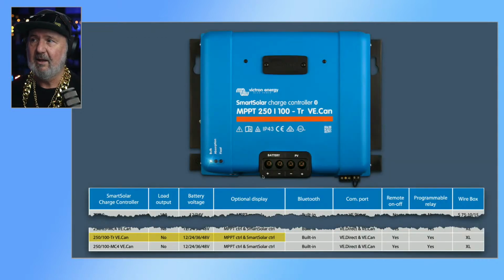So is that happening? Very popular products such as Victron's Smart Solar and many other brands do not have this functionality yet. Correct me if I'm wrong, guys, because I'm not a Victron installer these days, but only the RS450s had an earth fault detection function, from my memory, which are their big units. They have a 100 and 200 amp output, and they also had a 450 volt input, so they can definitely go well into the LV range. So you're connecting a 48 volt, in this case, it can go down to 12 volts. You see the range at the bottom there. A 12, 24, 36 or 48 volt battery to an LV array, you've now got a potential, under fault conditions, of having LV turn up on that battery terminal. And that's why it's very important to have earth fault detection.